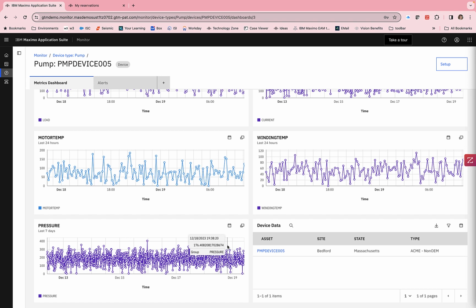For example, if the average pump pressure is declining while the average flow is increasing over time, this warrants an investigation as to whether there are leaks in the pipeline. Based on such knowledge, an operations team could investigate whether the pump needs to be serviced more frequently.